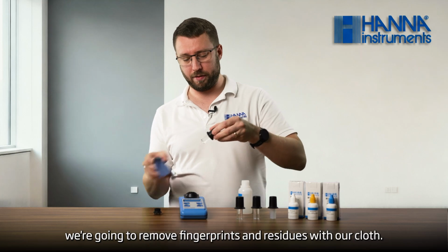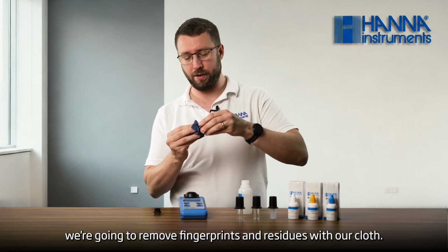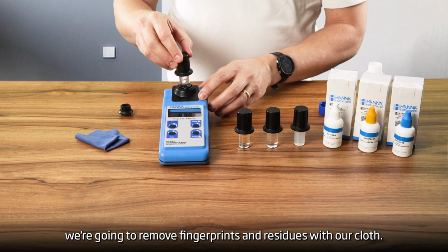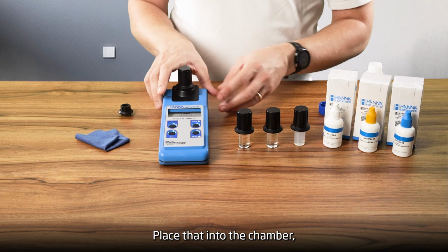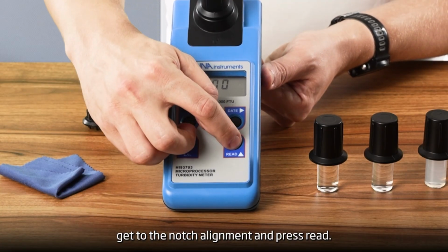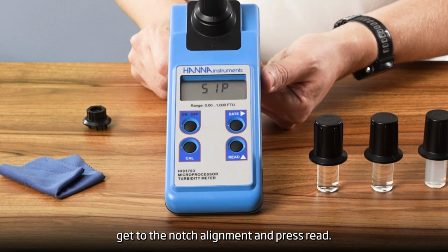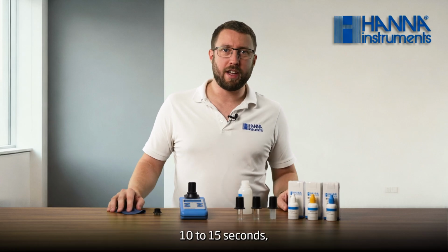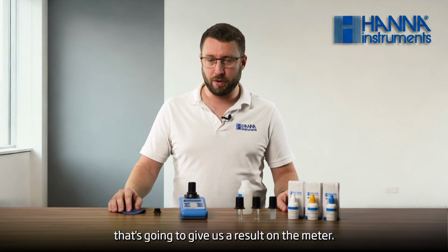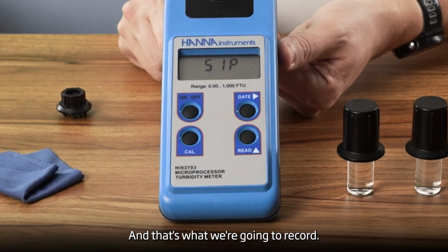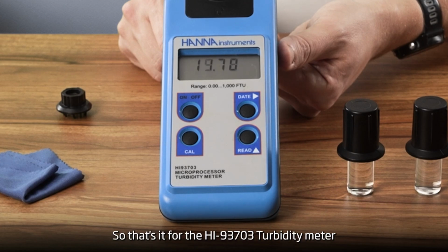And again, we're going to remove fingerprints and residues with our cloth. Place that into the chamber. Get to the notch alignment and press read. And after, again, 10 to 15 seconds, that's going to give us a result on the meter, and that's what we're going to record. So that's it for the HI-93703 Turbidity Meter.